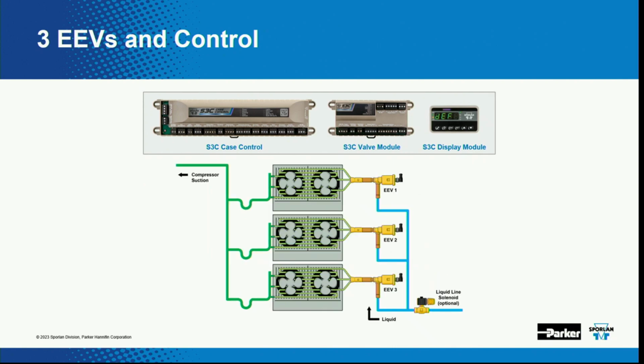Right. So here's another shot, and this is just showing again basically what we just talked about. You can do 3 stepper motors with just a controller and a valve module. And like I said, we can control discharge air on each one of those coils. Now in this case, the liquid line solenoid is going to be hitting all those at once. So it's going to look at the main valve. Actually, let me back up. It's using an aggregated discharge air to make the call as to how it's going to modulate that valve. So it's basically doing an average.